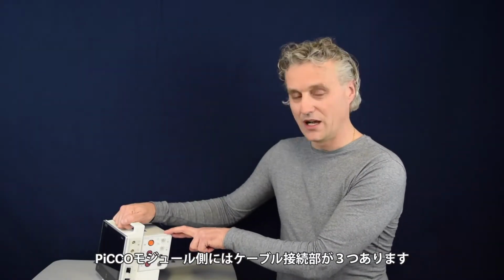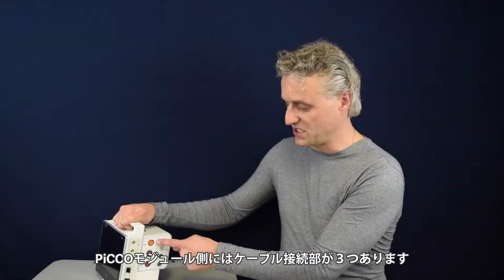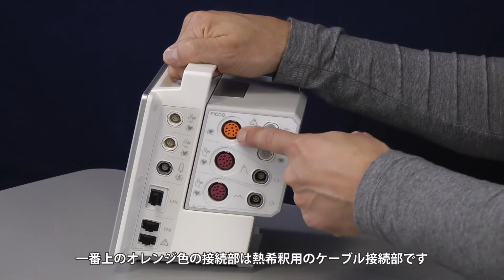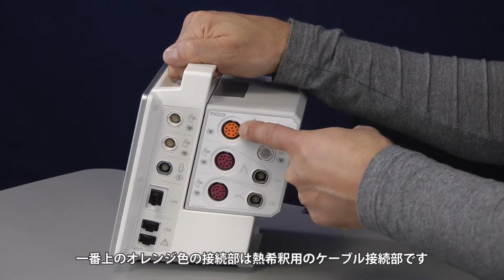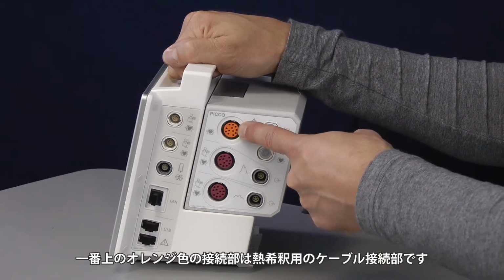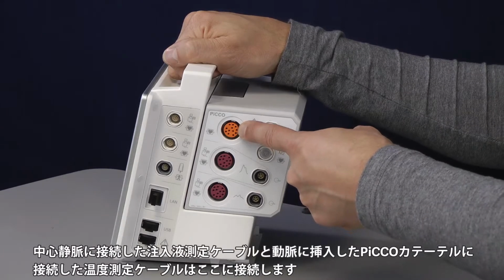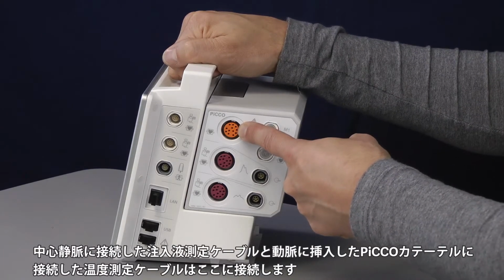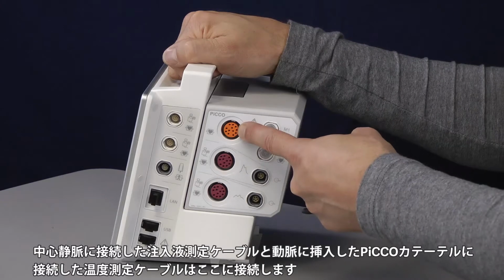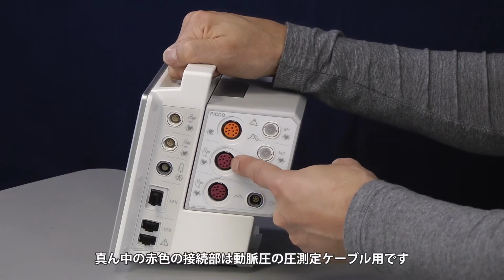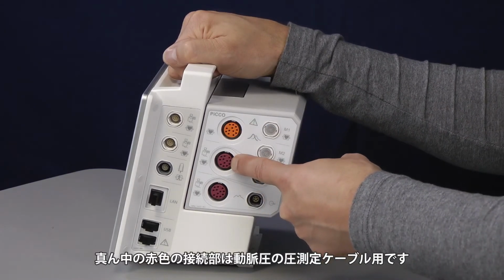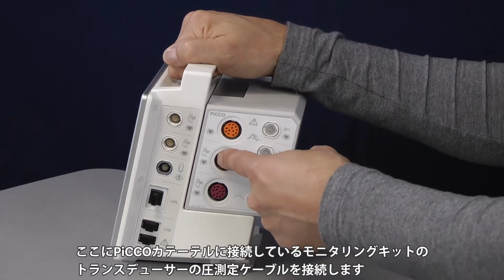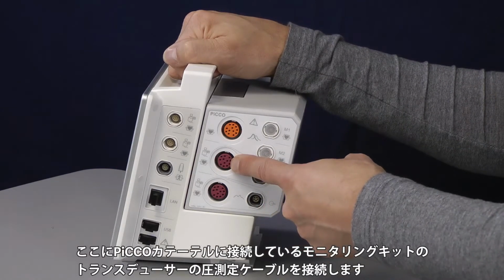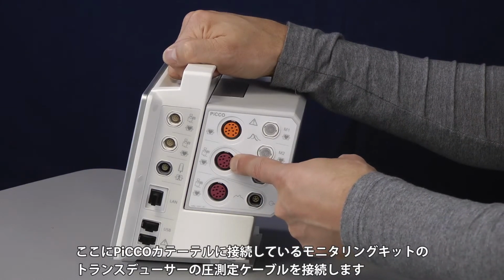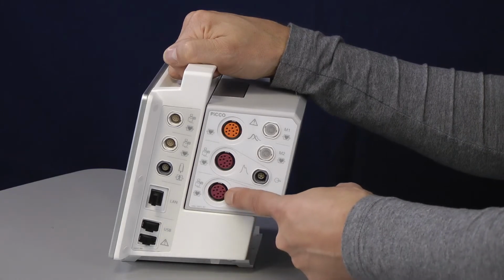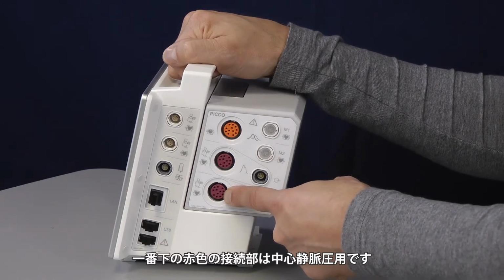The PiCCO module on this side has three connections here. The first one, the orange one, is for your cardiac output connection. The cable with cardiac output and with the injectate sensor will enter here. The red one here is for your arterial pressure. Here you can put in your arterial pressure connection of transducer. The bottom you can see here is for your central venous pressure.